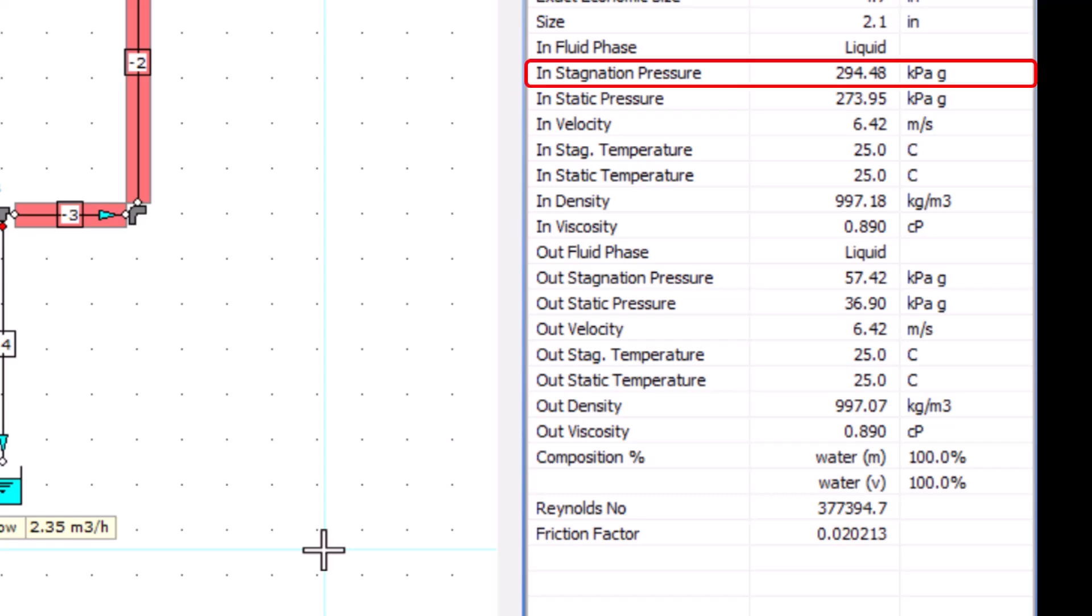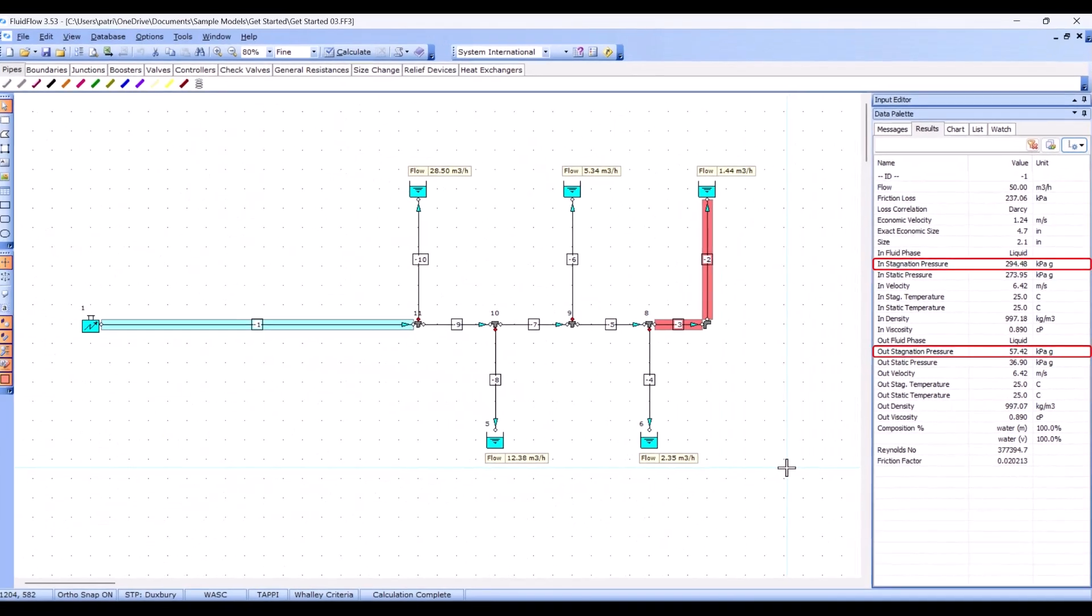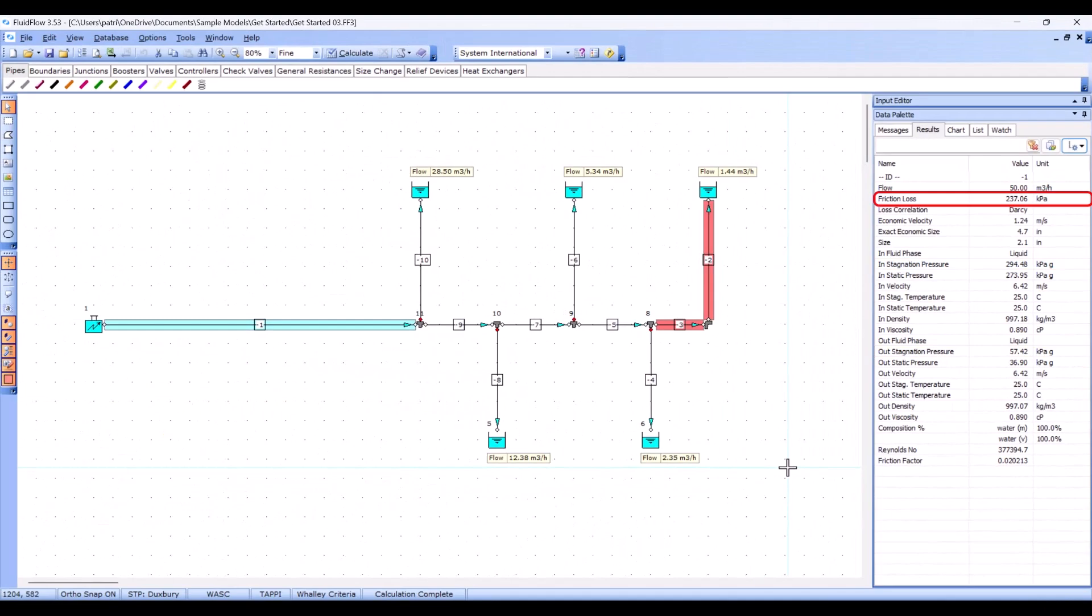So for example, we can see the stagnation pressure at the start of this pipe is 294.48 kPaG, and the pressure at the end of the pipe is 57.42 kPaG. The difference between the two should equate to the friction loss in the pipe.